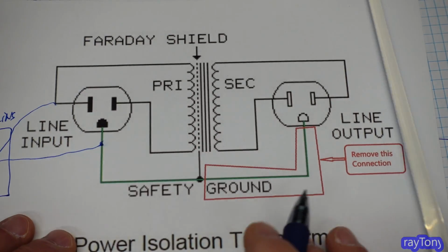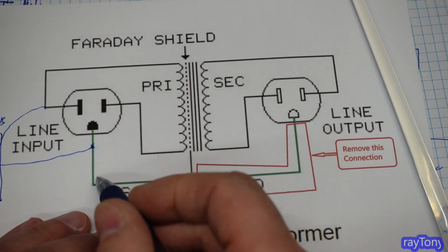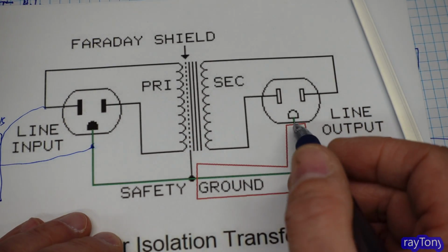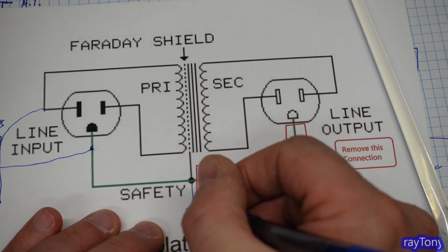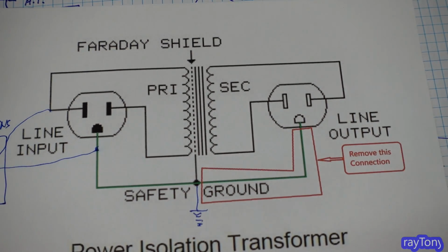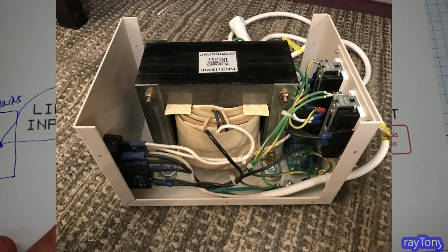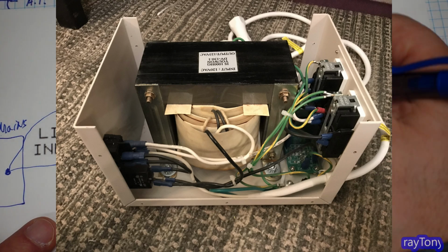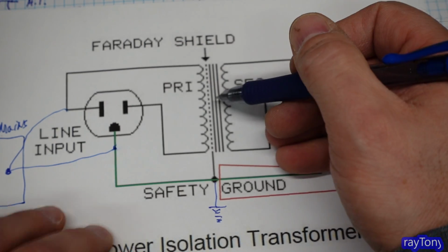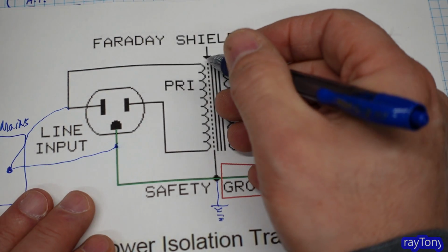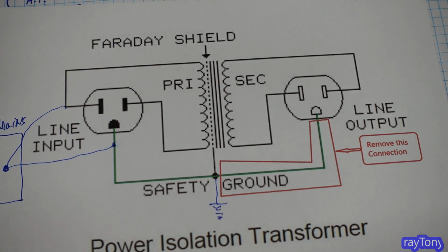So look what they've done: all the grounds are connected, and they even go to the chassis of the box the thing's mounted in, grounding it as well. Then there's a shield, which is fine—that's electrically isolated from all this. This is a noise shield, which is why they call it a Faraday shield.